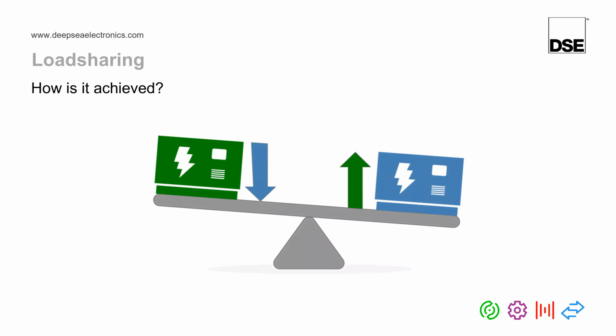However, once we've done synchronizing, what happens next? Well, normally the reason why we are synchronizing multiple generators together is so that we can load share with multiple generators. Load sharing is basically just making sure that multiple generators can share the load between them. And the way the DeepSea module does load sharing is it doesn't necessarily share the load equally between the generators, because if you have different sized generators, what the DeepSea module will try to do is make sure that each generator is producing the same percentage of power.